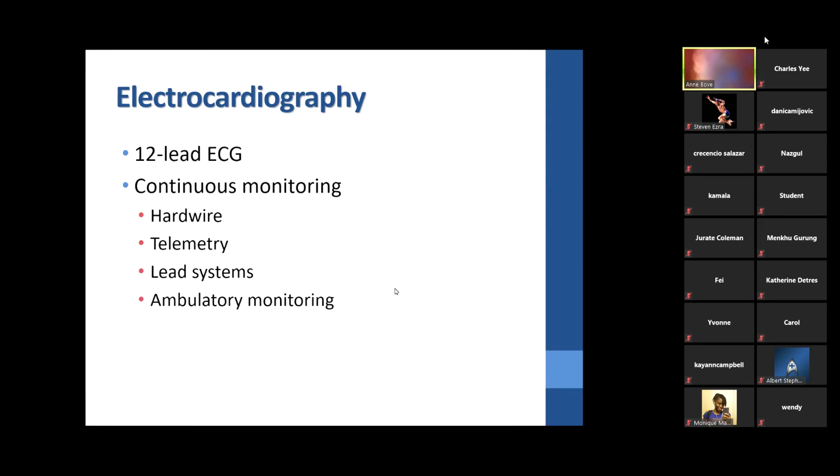And interestingly enough, when we started to initially use telemetry, one of the things that we found was the systems were going down. And the real reason why the system was going down was because the FDR drive was next to the hospital. And the way that the cabs were communicating in terms of their wavelengths were interfering with the telemetry. So there had to be a different wavelength established and certain guidelines so that everybody could communicate and get the information that they needed.